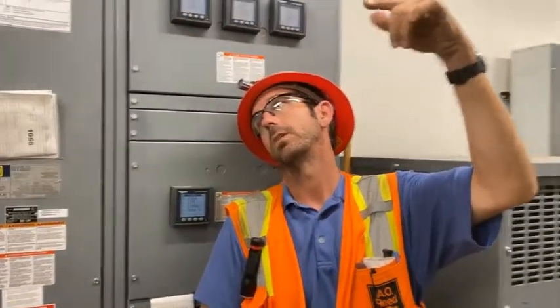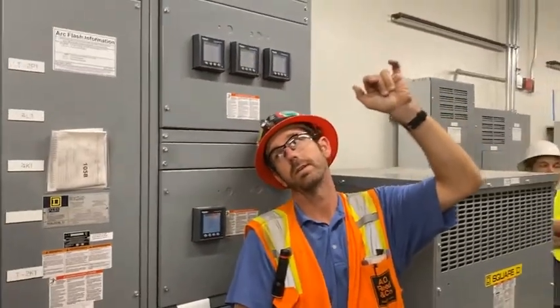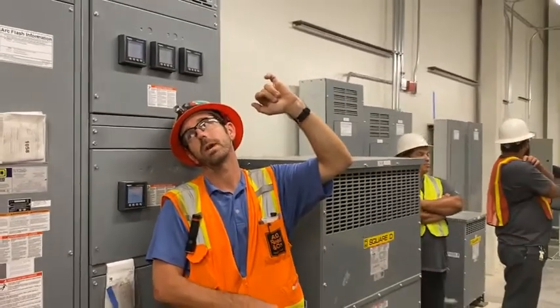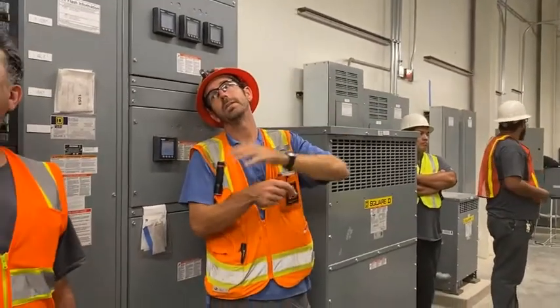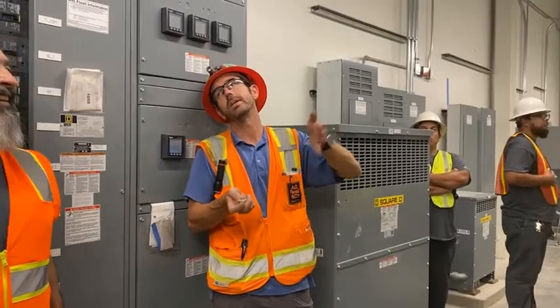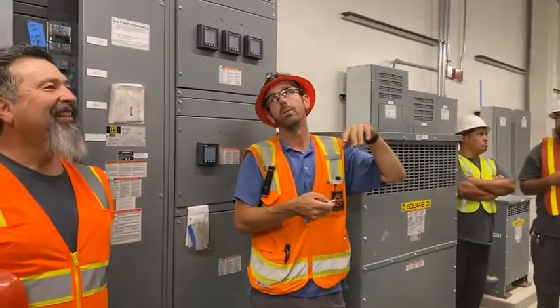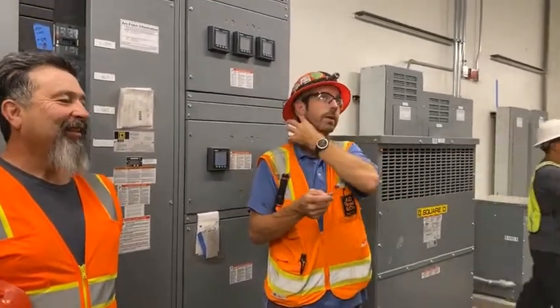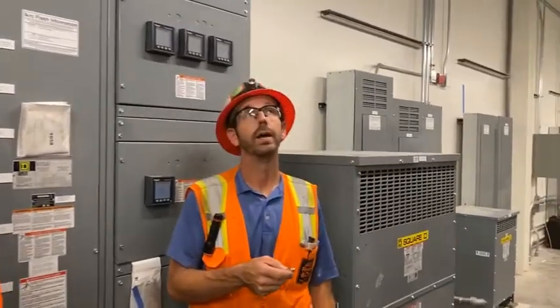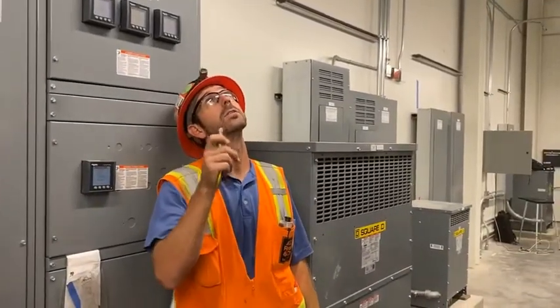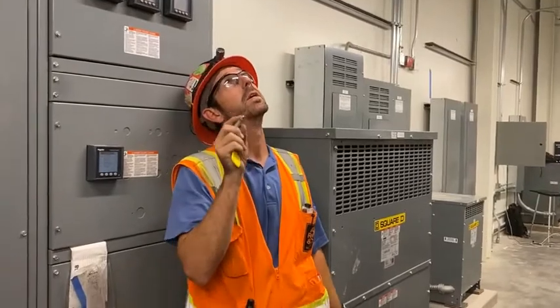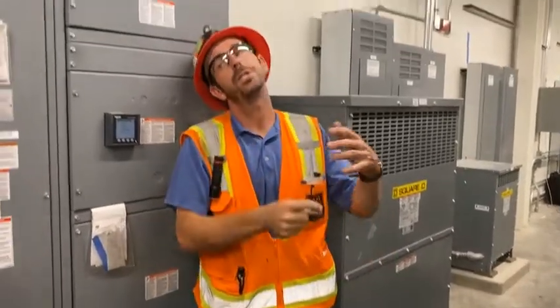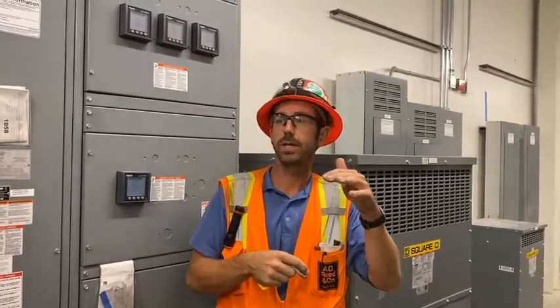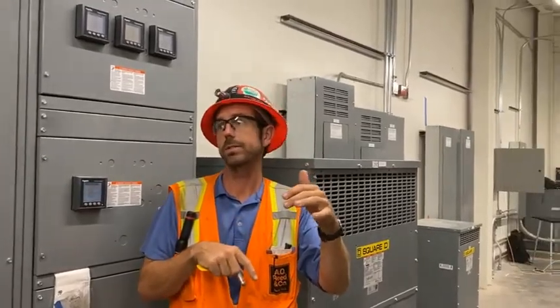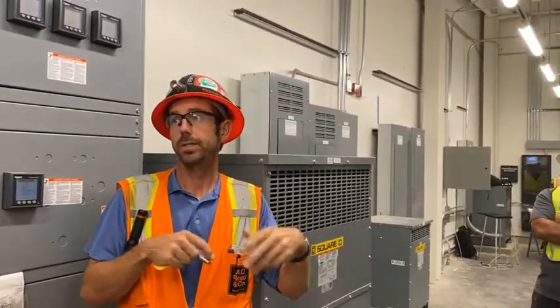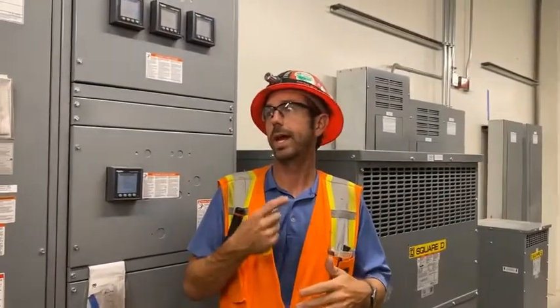Oh, 277? Yeah, so these fan coils are 277 volts, single phase. Okay. Single phase. I mean, single phase, 277 is only single phase 480. Yeah. Okay? Well, it's one leg of 480. It messes you up. Yeah, it won't feel good. Okay? So these are 277 volt fan coils. Remember the sheet I handed out to you guys? I said there is a list of all the fan coils with condensate pumps. Yes. And Building D, your guys' building, this is the only unit that has a condensate pump.